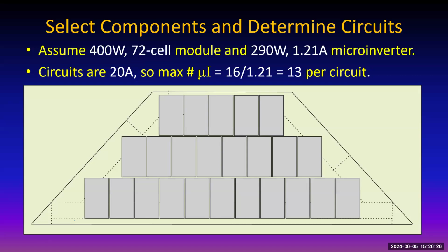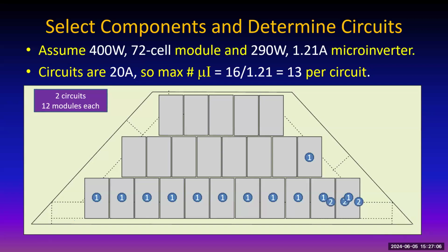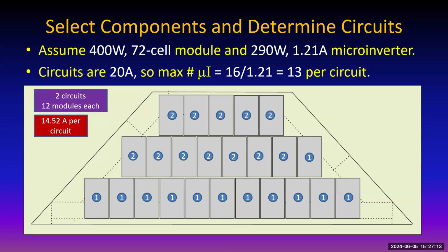So here's our system that we laid out previously, and we've got 24 modules here. So we can have 12 modules each, and that'll work just fine because we can't have more than 13. We could have 13 and 11 if we wanted, and that would still add up to 24, because each microinverter is its separate inverter that's totally independent of the operation of the other ones, other than under a rapid shutdown command where they all have to shut down. All right, so we can do 2 circuits with 12 modules each if we do it like this, maybe. And that'd be the first circuit, and then here's our final circuit here with 12 modules. And that adds up to 14.52 amps per circuit, well within the 16 amp requirement.